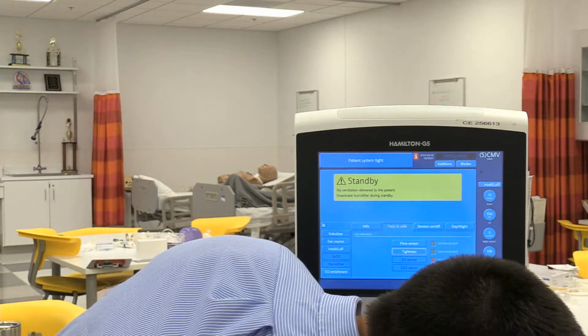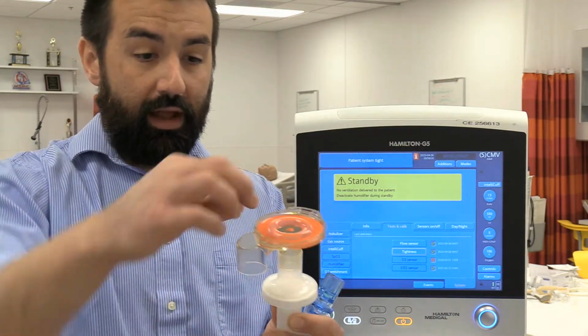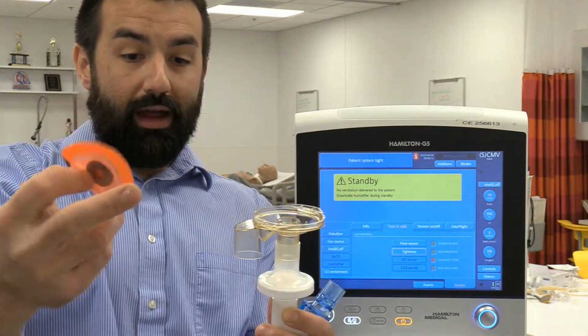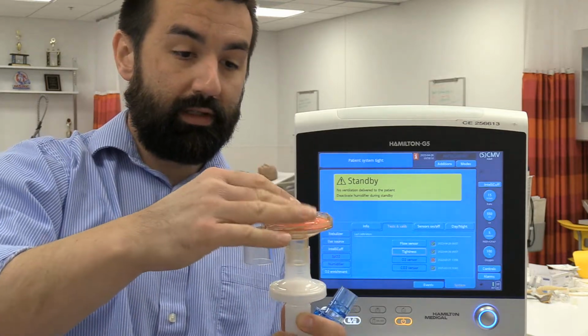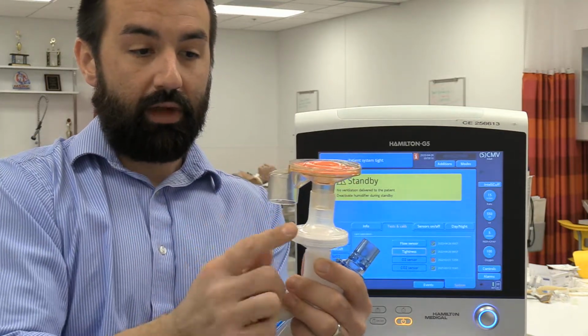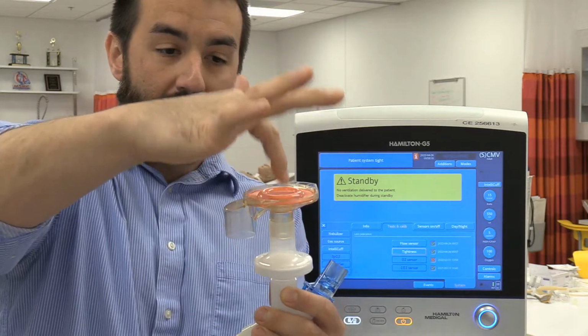And I'll go ahead and kind of show you that here. On the expiratory side of the ventilator, you have this little weighted diaphragm that sits on top of this exhalation mechanism, okay, and vents the air out. So it's got a little pin that controls the exhalation valve and allows for PEEP and things like that. If you have this in upside down or anything like that, you're going to have problems.